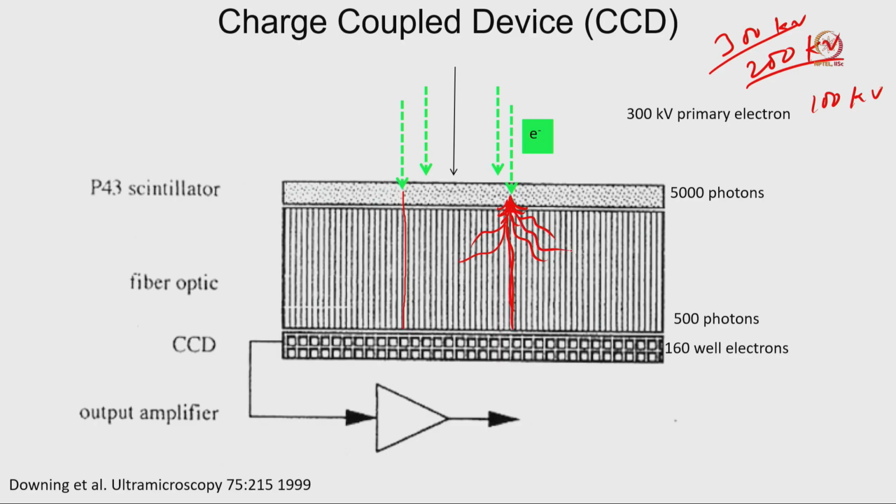It will not follow this straight line all the time. So, it will follow different types of trajectory, and a couple of electrons will go back and hit this. Then what will happen? It will consider this another single event, and this will start generating the electrons in all the directions. So, sometimes those electrons have less energy than these electrons, and that will create more noise.